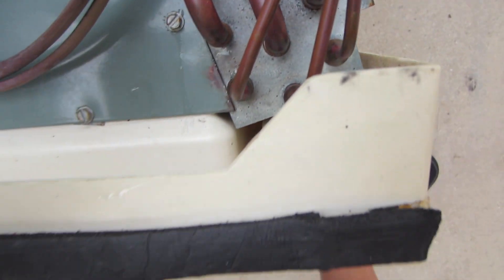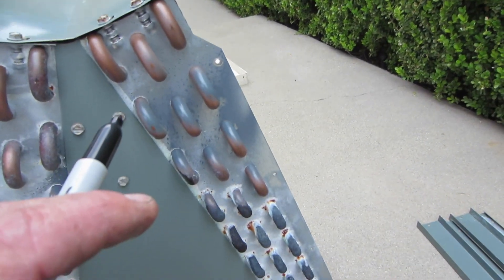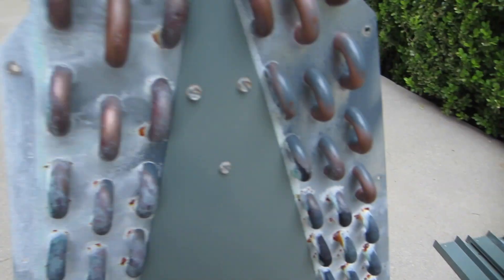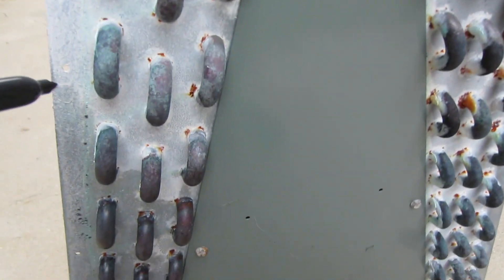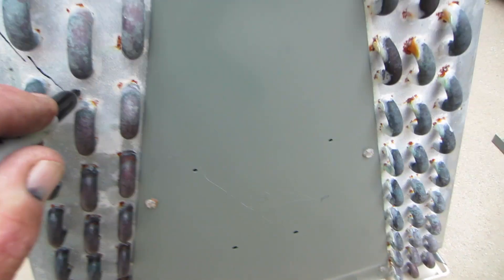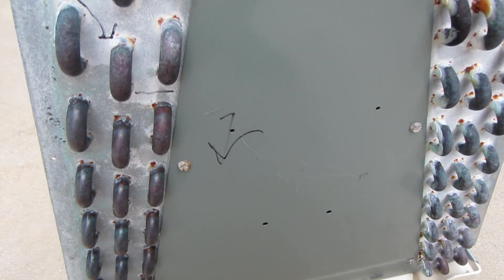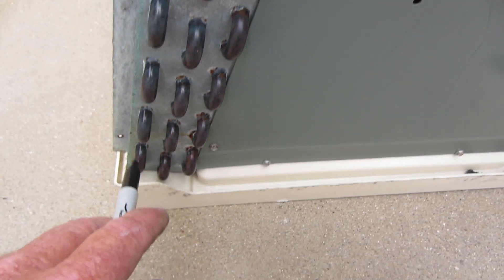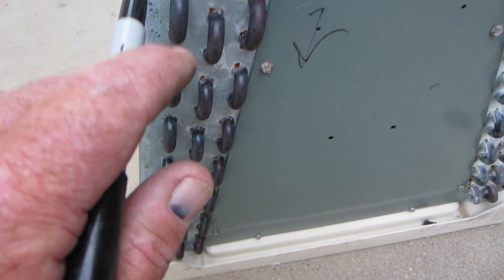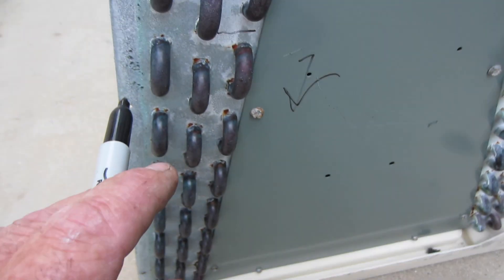And oily in here too. Looking at the back side — this area is fine, no leak here, no leak here. Right here is where our oil staining starts on the sheet metal, from here down it's bad. You can see it all the way down — it's all darker. You can see the color contrast from dry to an oil sheen.